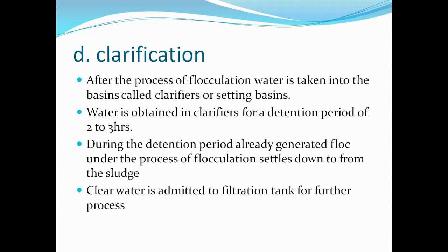In the clarification process, the water after the flocculation process is taken into basins called clarifiers or settling basins. Then in the clarifier basins, the water is kept for a 2 to 3 hour detention period, and then the flock formed in the flocculation process settles down and forms the sludge, and clear water is admitted to the filtration tank.